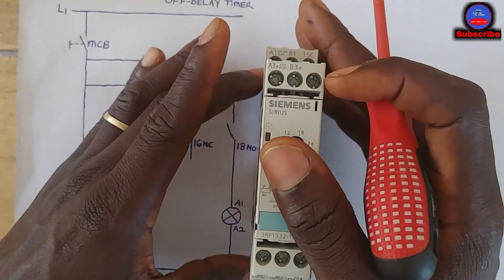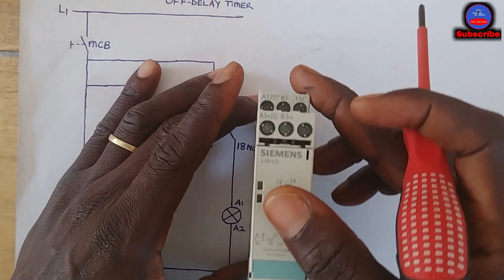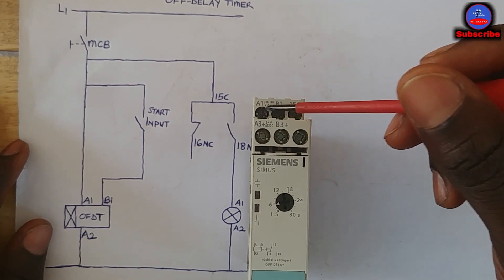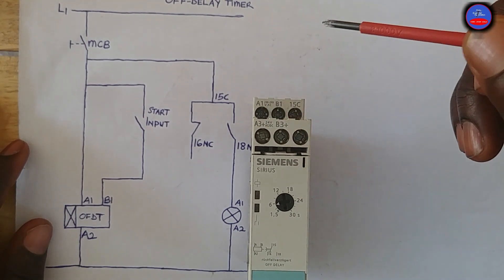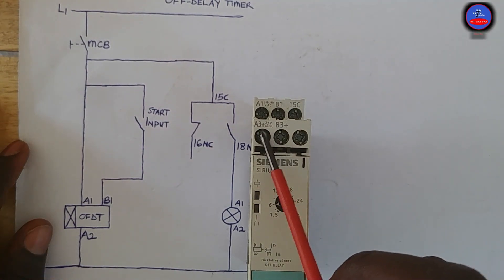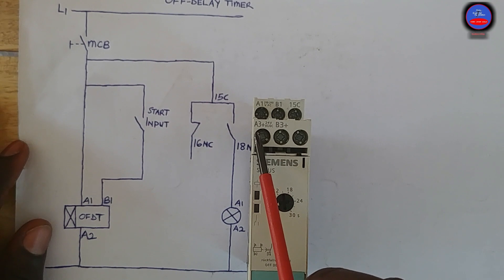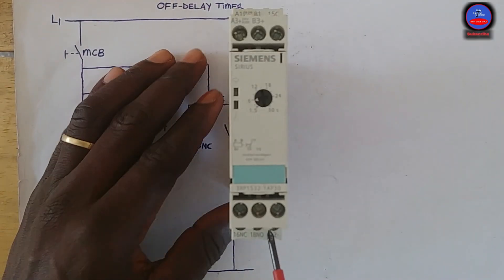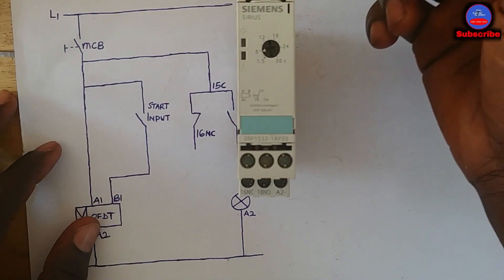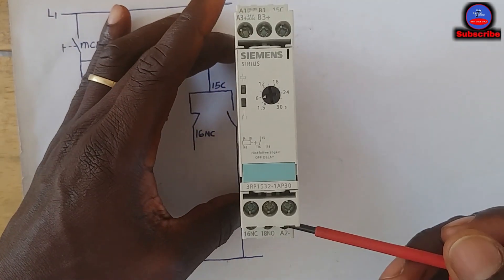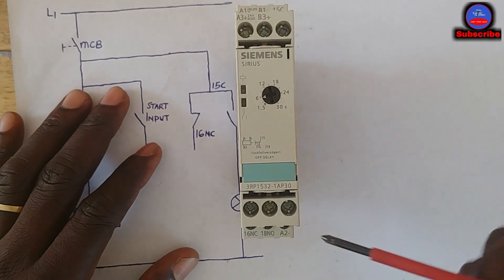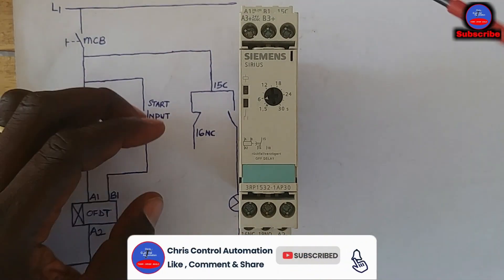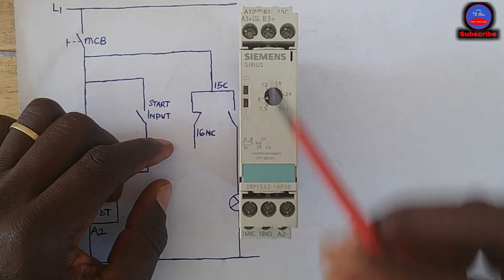This timer operates on two voltages: AC and DC. Down here we have terminal A1 — A1 is for 220 to 240 volt AC, so if you want to use the timer on AC you use this side. Up top we have terminal A3, which is for 24 volt DC. The A2 terminal is common to both AC and DC. So for DC the coil terminals are A3 and A2.